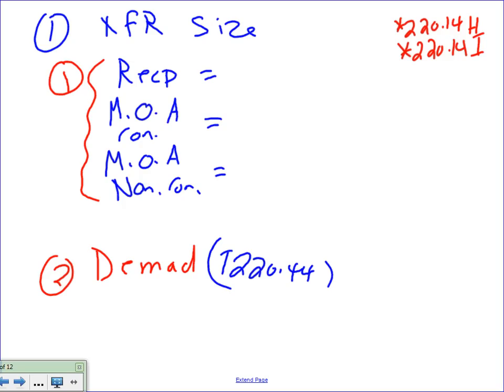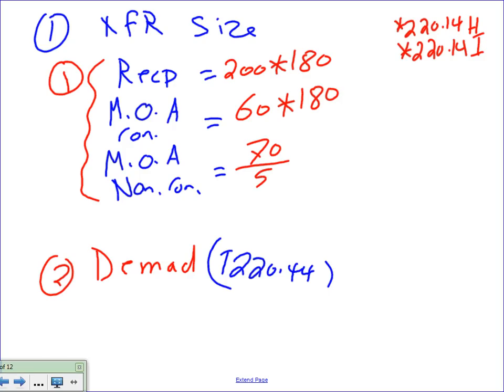180. So I have 200 multiplied by 180 volt-amps, right? Then multi-outlet assembly continuous. This one is MOA, not Mall of America. This is multi-outlet assembly continuous, and I have 60 of them. If they're continuous, you have to multiply by 180 for every 1 foot. Then multi-outlet assembly non-continuous: take every 5 feet, divide by 5, and then multiply by 180. You guys remember that? We did it in the fall. How to do the calculation for receptacles and for multi-outlet assembly, right?